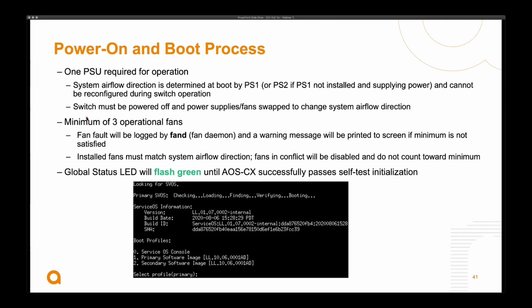Second prerequisite, you have to have a minimum of 3 operational fans. If you do not meet that requirement, a fan fault will be logged by the fan daemon, and a warning message will be printed to the screen if you have less than 3 operational fans. As noted, all installed fans have to match the system airflow direction. So any fans you have installed that don't match the switch running airflow direction will be disabled and not count toward that 3 fan minimum. So that will be logged as a fault until the fan, if it's a failed fan, is replaced, or if it's a fan that doesn't match the airflow direction, until you replace it with the proper airflow fan.